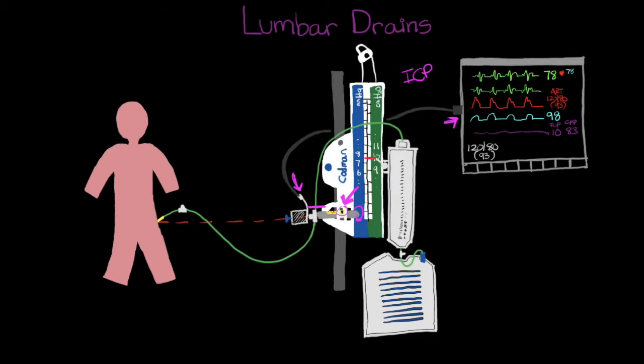Now, once we know that we have the laser leveled at the insertion site and we are still off to the drain on the panel stopcock, what we want to do is drop the drip chamber down to the 0 level. So up on the drip chamber up here, there's going to be another twist lever here that you would twist and untwist to either tighten or loosen and be able to raise and lower your drain. So what you're going to want to do is lower your drain down until you're at the 0 mark on here.